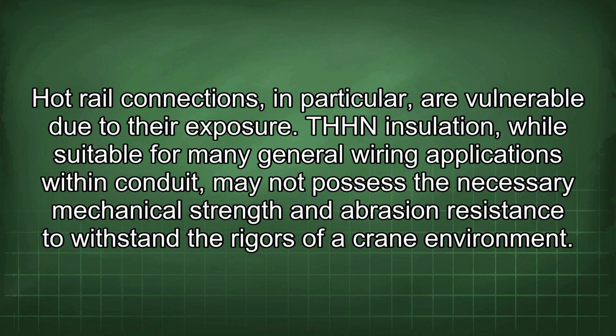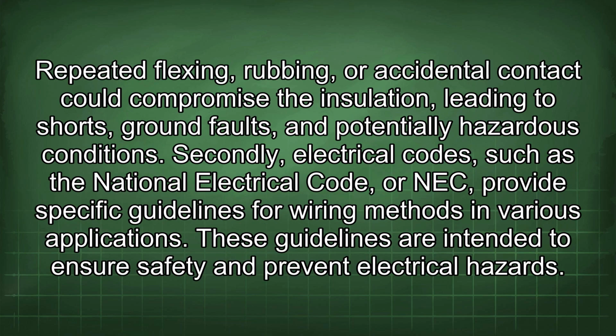THHN insulation, while suitable for many general wiring applications within conduit, may not possess the necessary mechanical strength and abrasion resistance to withstand the rigors of a crane environment. Repeated flexing, rubbing, or accidental contact could compromise the insulation, leading to shorts, ground faults, and potentially hazardous conditions. Secondly, electrical codes such as the National Electrical Code, or NEC, provide specific guidelines for wiring methods in various applications. These guidelines are intended to ensure safety and prevent electrical hazards.